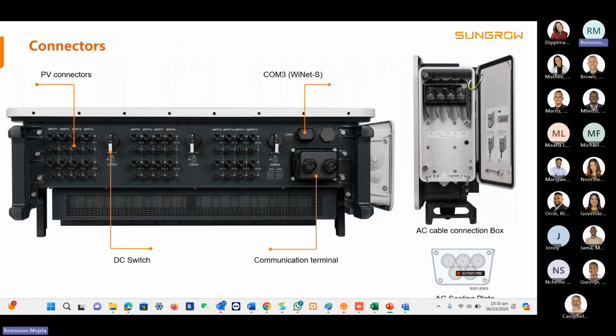Then we have the connectors of the structure of the 125. So this basically is the 125. You have 3 DC switches, and those are the MPPT inputs at the bottom. And then we have your comms plug-in, but these comms are only compatible with the WiNet-S or the Logger 1000, and the Logger 1000 doesn't connect on COM3. It goes directly to the bus of the A1B1 of the RS485 of the inverter, which I'll explain later. So basically, this is just the structure. These are the DC switches. This is your PV input. This is your comms for the WiNet-S, and then you have your AC cabinet, which is on the side.